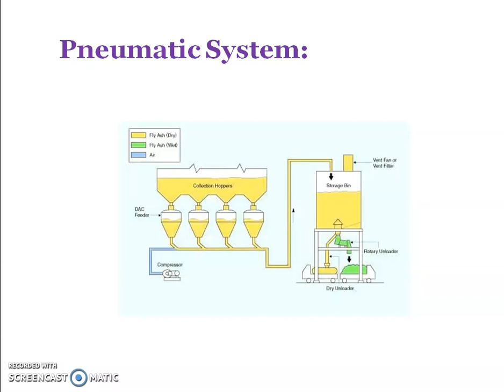The ash carrying capacity of the system varies from 10 to 25 tons per hour. Some of the advantages are no spillage and rehandling, and it is highly flexible. The cost of the plant per ton of ash discharged is very low compared to the other systems. The disadvantages are that it is more noisy than the other systems, there is a large amount of wear in the pipe work, and high maintenance charges are required.